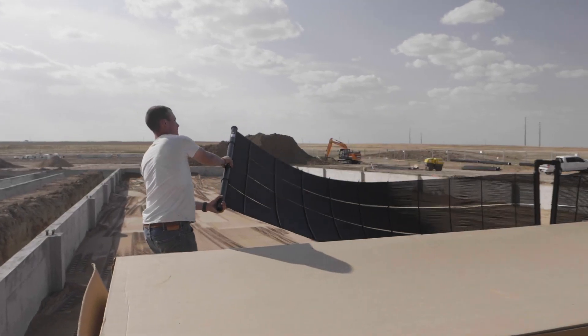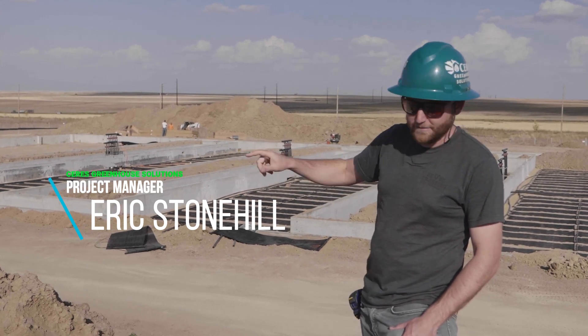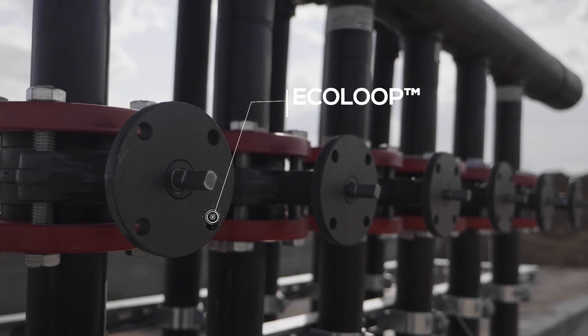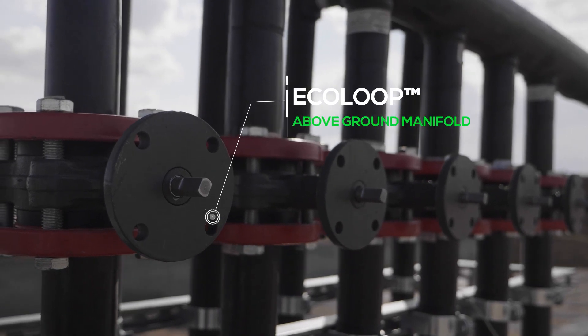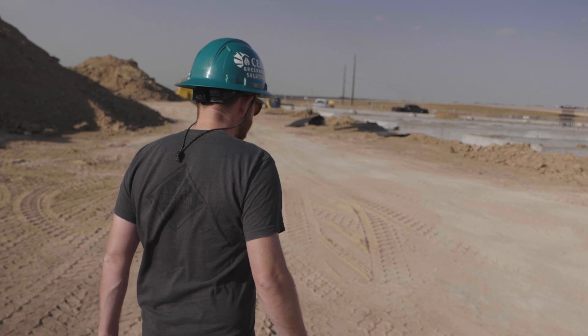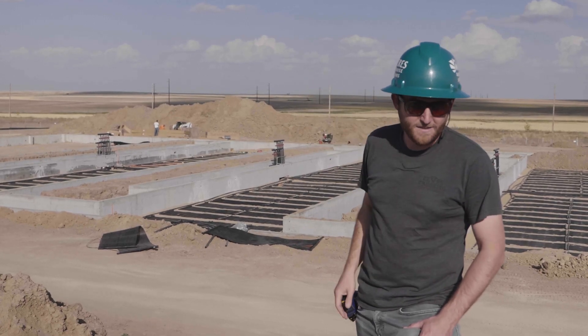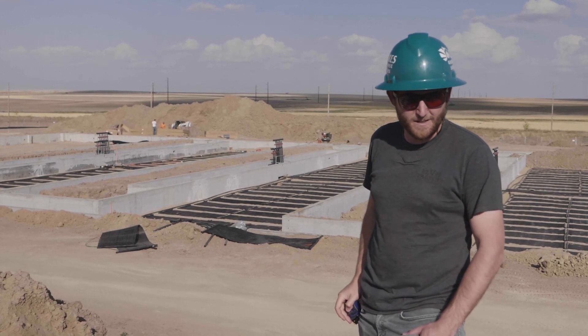Each Ecoloop mat installation gets six inches of sand below, six inches of sand above, and is four feet below the top of slab grade on the interior of the greenhouse. That serves as our heat sink during the day where we store our heat, and at night we pull from that reservoir of heat underground and put it into the air in the greenhouse for heat.